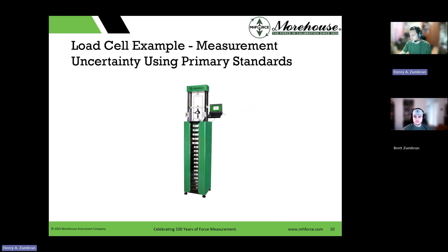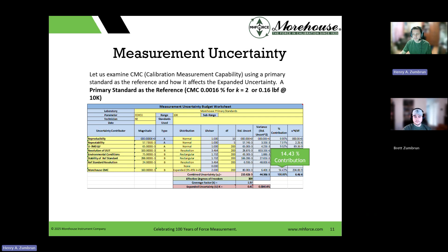Morehouse CMC would be the reference uncertainty of our dead weight machine. That's really low. Our reference standard, when we put it in our dead weight machines, is 14.43% of the overall contribution to everything for this load cell. This is using the Welch-Satterthwaite equation, which is found in JCGM. Just look at that, say, okay, I've got my repeatability and all the other stuff, for the 10,000 pound load cell. Now, do the same thing.